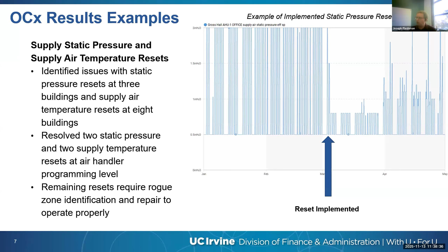We had a couple buildings with static pressure reset issues and 8 buildings with SAT issues. We resolved a couple of those static pressure and supply air temperature resets. What often happens, though, is you have multiple rogue zones that you have to get people out in the field to repair and operate properly, and those take a little more time to resolve.